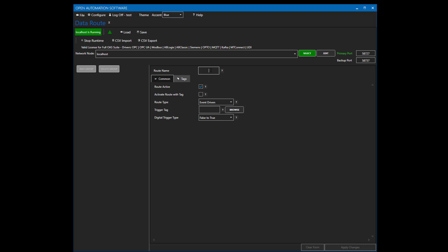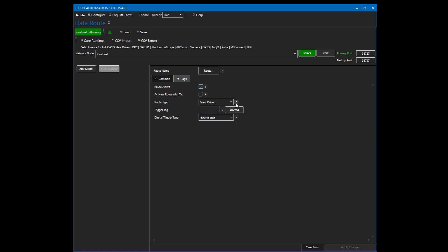The first thing we'll do is start the configure application and manually set up a data route. Going to Configure Data Route, here is where we define the multiple tag data route feature. We give it a route name — I'm going to call it Route1. With the route type, we can set it to be event driven, based upon a Boolean tag or integer tag that transitions non-zero. For a Boolean tag, we determine whether to trigger on a transition from false to true, true to false, or both.